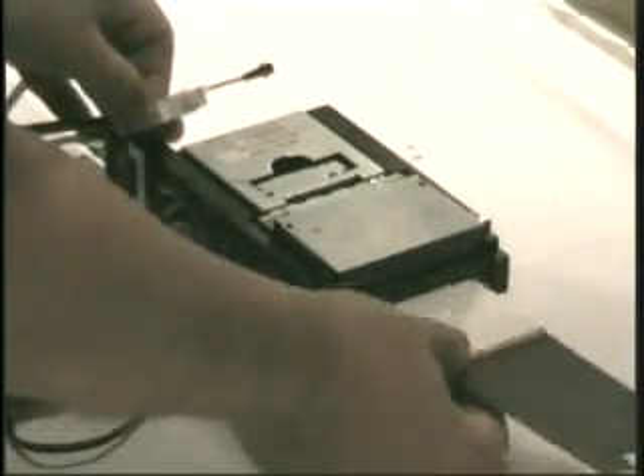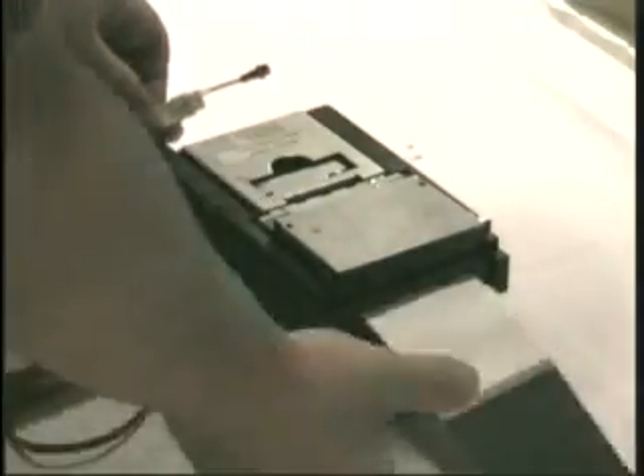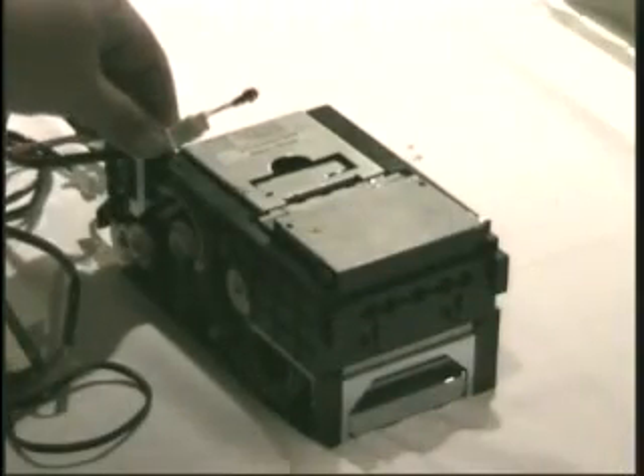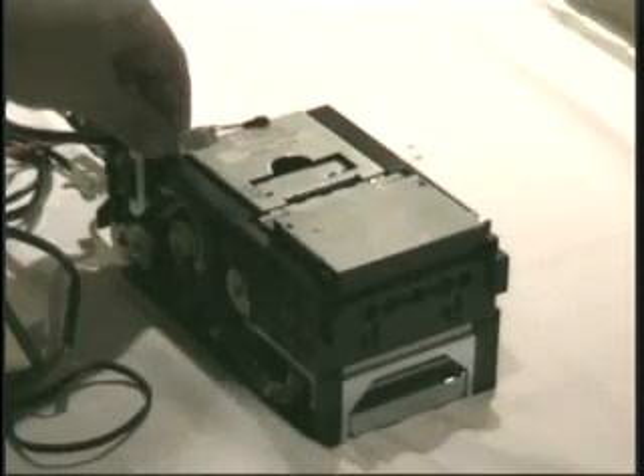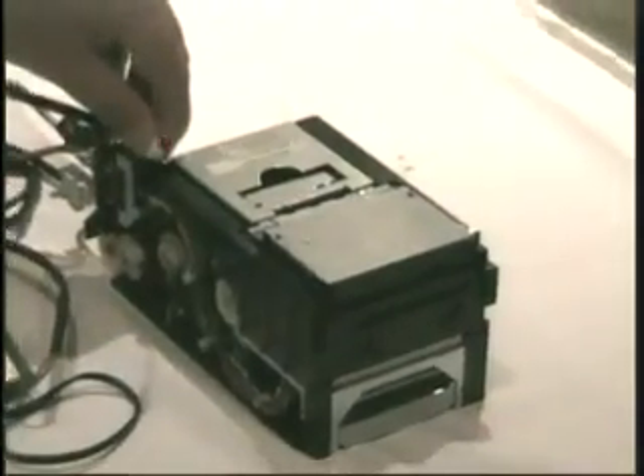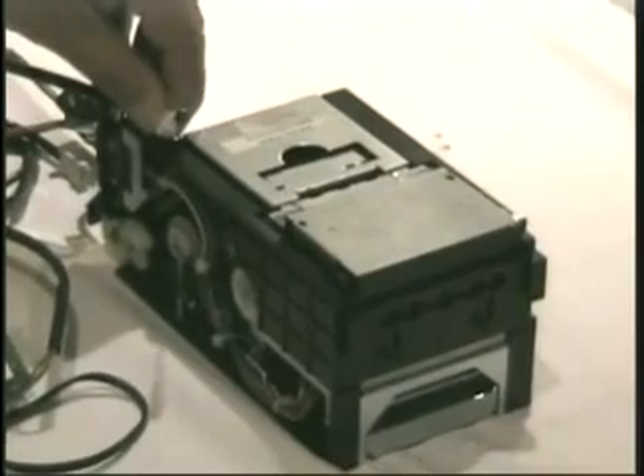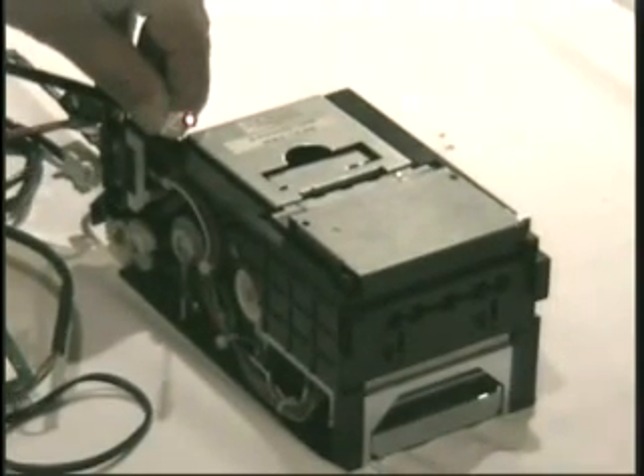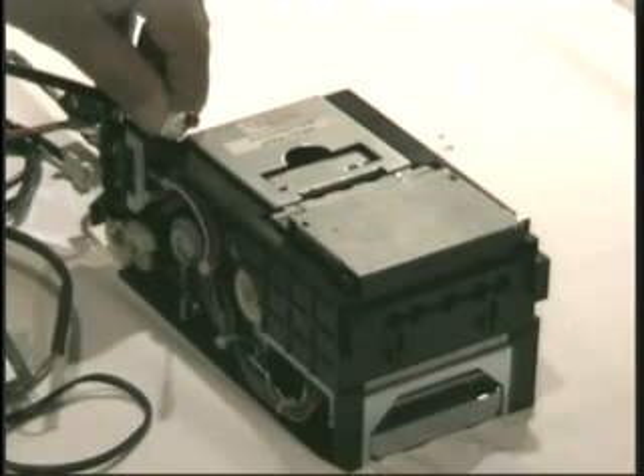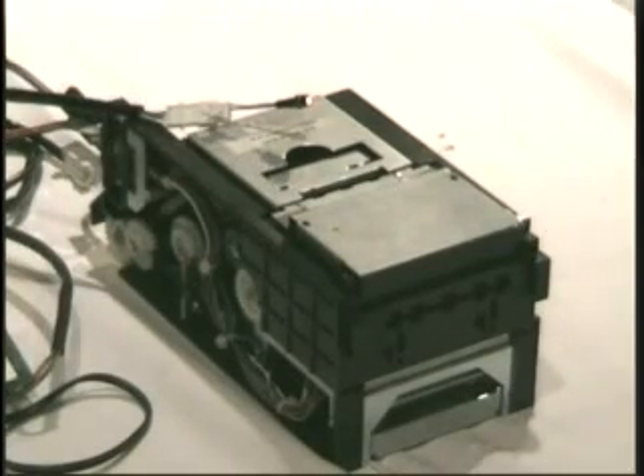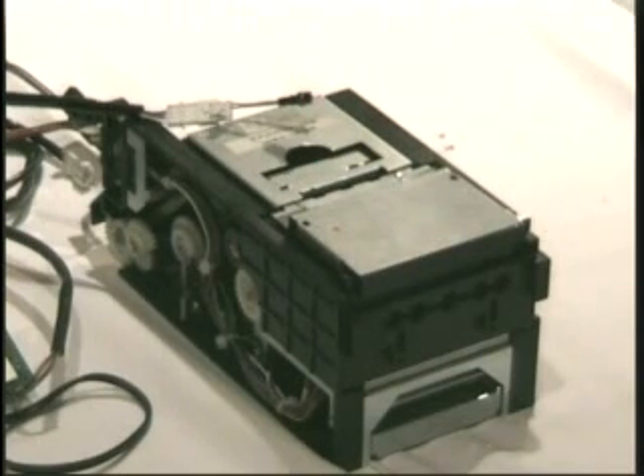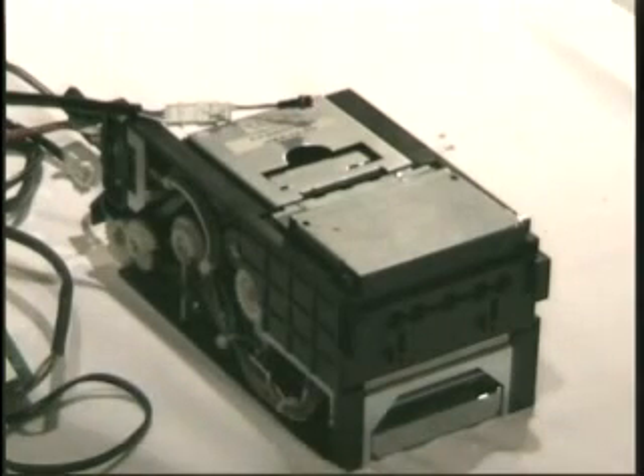If it has a problem with calibration, if it can't reach calibration, instead of getting that rapid pulse, and I'm just going to simulate a problem here by feeding the paper backwards, it's going to give you a code. Where are we at? There we go. Certain number of pulses, then it's going to pause, and then it's going to repeat the code. In this case, we're getting 5. Should be 5. Gain error. White level adjustment. If you fed the paper correctly, replace the upper sensor board. Basically, they build a lot of onboard stuff to tell you, if you get this number of flashes, this is the error code, this is what's wrong. That's the one thing I like about this.